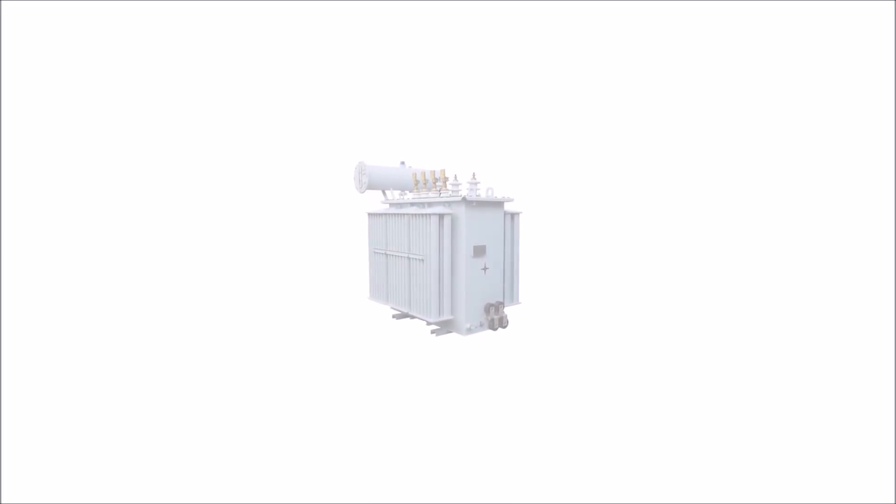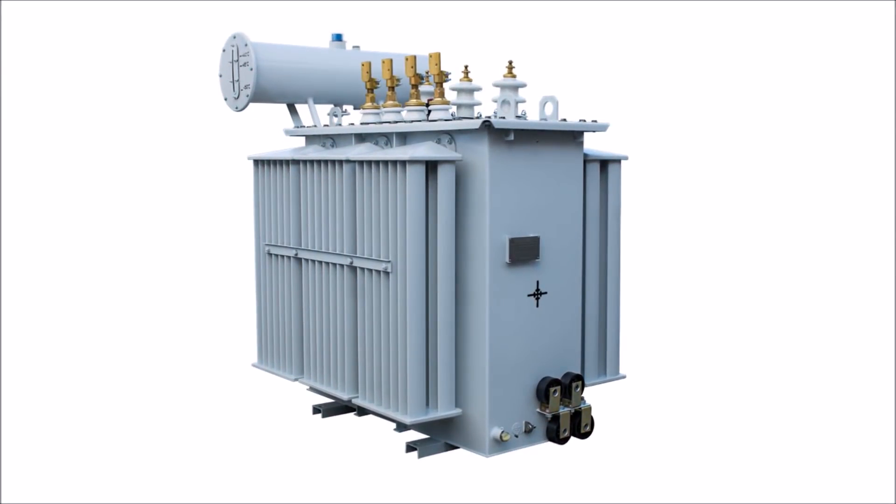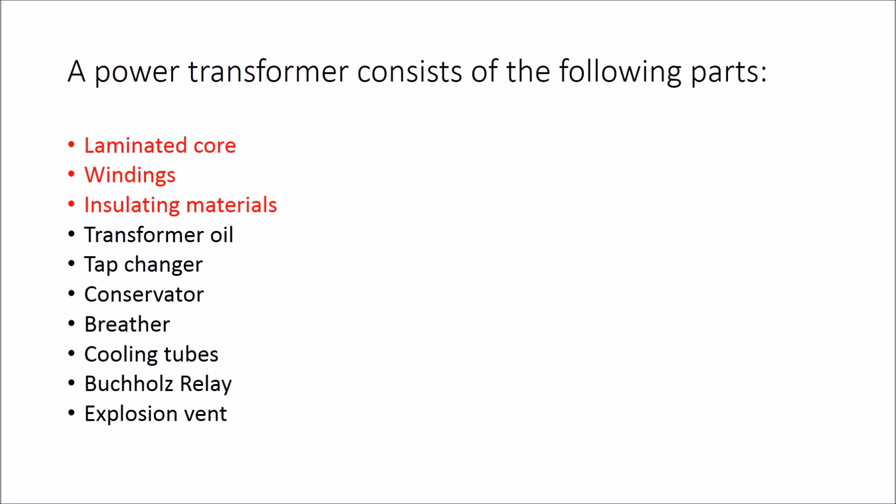A transformer is an electrical device that transfers electrical energy from one circuit to another by electromagnetic induction. It is used to step up or step down AC voltages. A transformer consists of a laminated core, windings, insulating materials, transformer oil, tap changer, oil conservator, breather, cooling tubes, Buchholz relay, and explosion vent. Of these, the laminated soft iron core, windings, and insulating material are the primary parts present in all transformers, whereas the rest are found only in transformers having a capacity of more than 50 kVA.